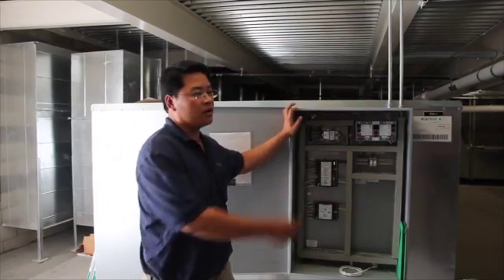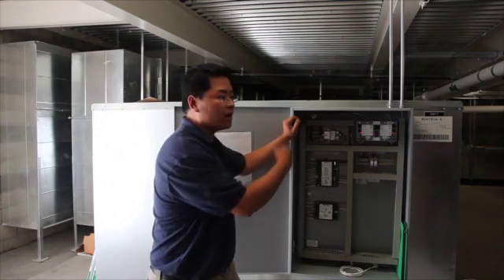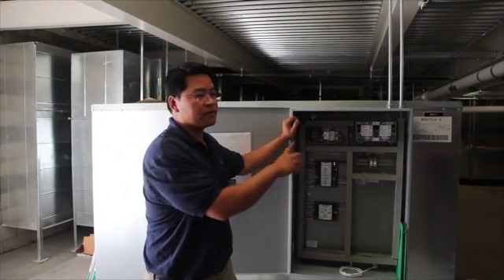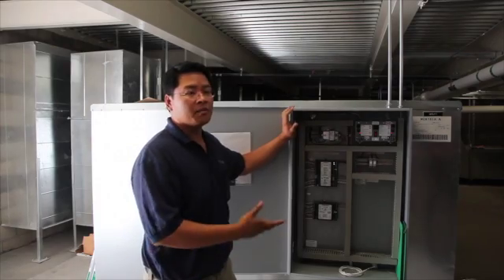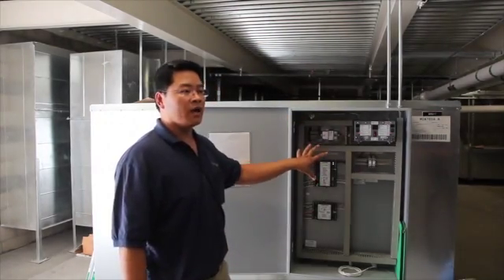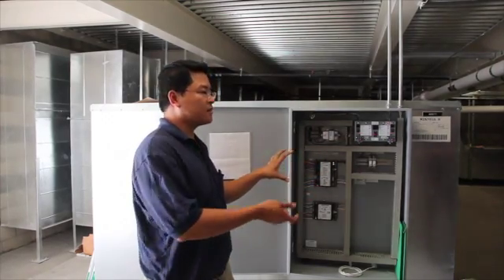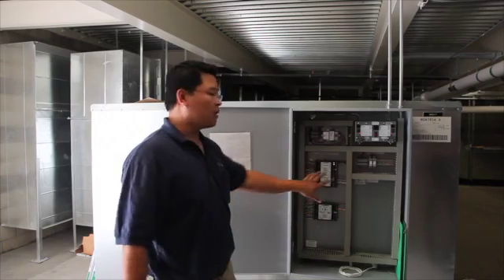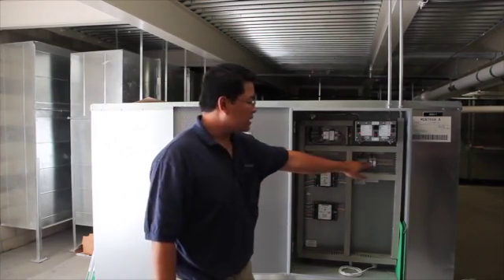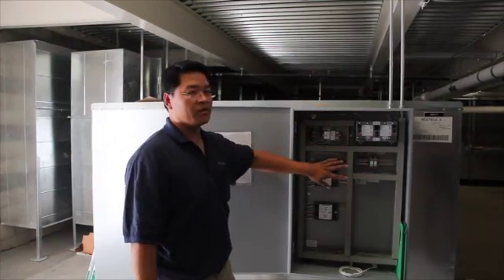The controller here locally, if it's tripped on software latches, you can reset the controller and it will clear for you. Or if somebody goes up here and didn't know they changed the filter or something like that, and they turn off the air handlers. They're linked together, supply and return. So if you turn off one, it should set that unit as an alarm and shut off both of them. But if it goes off that particular way, once the unit comes back or you finish your filter change or whatever and turn it back on, it won't run.